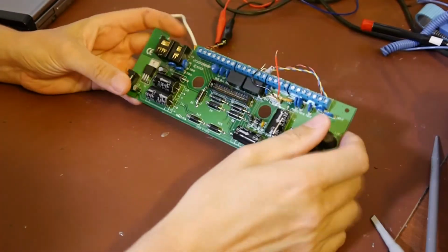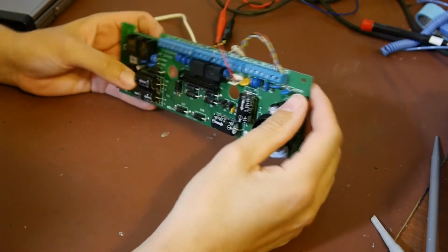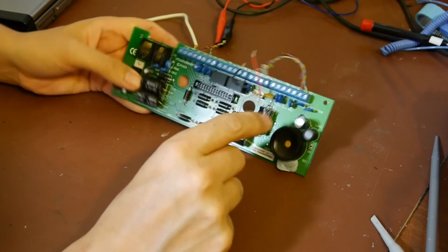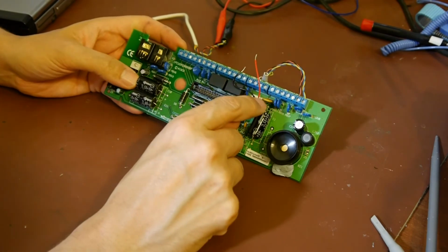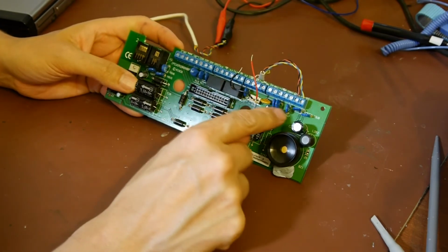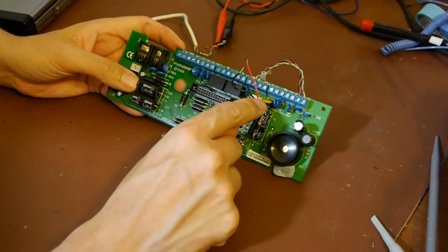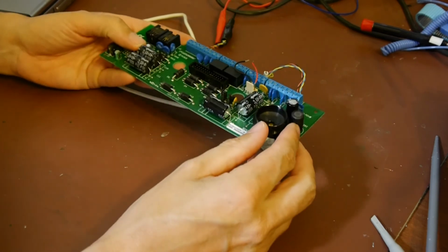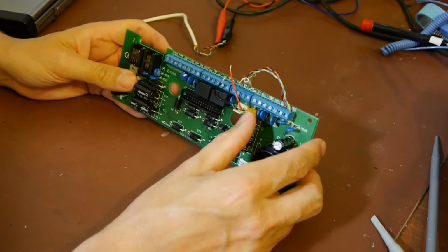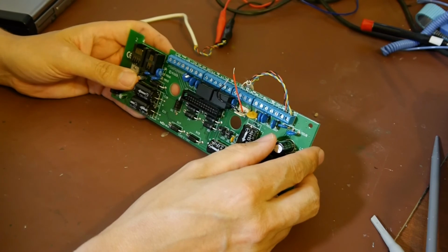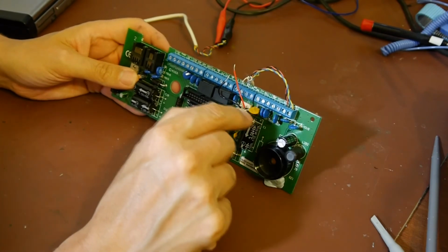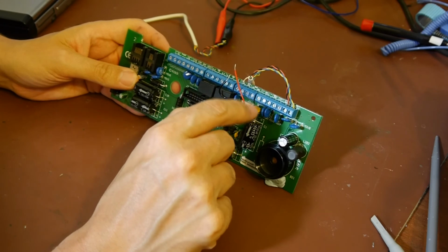A couple of other little things on here which I'll just point out. You see there's a brown thing here, cream colour, another brown one there. They look a bit like capacitors. In fact, they also look a lot like these MOVs. But these are electronic fuses which automatically reset. So if you've got a fault on the circuit and it's drawing too much current, rather than just blowing a fuse, they're a kind of thermal device, and they heat up inside and disconnect the circuit, and then when the fault clears they automatically reset.